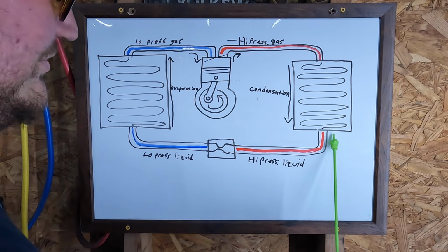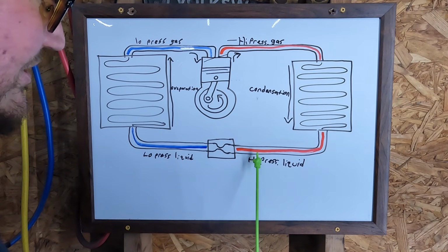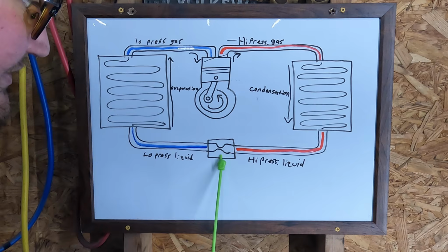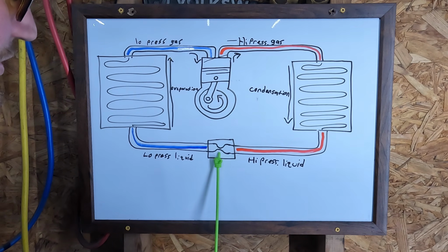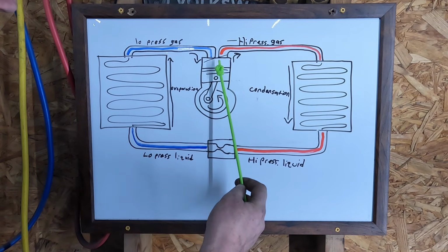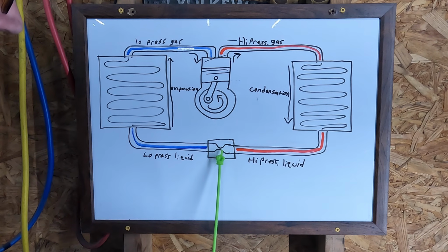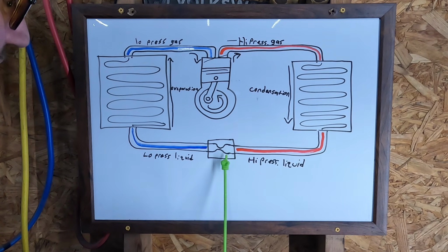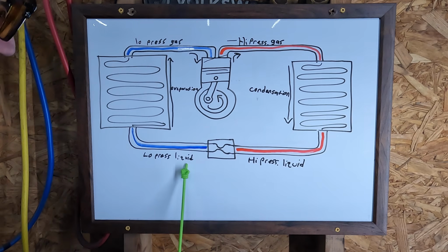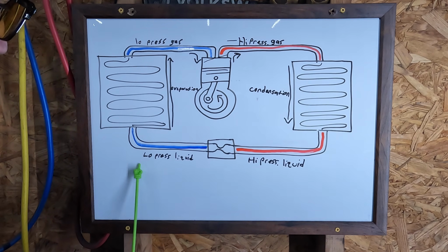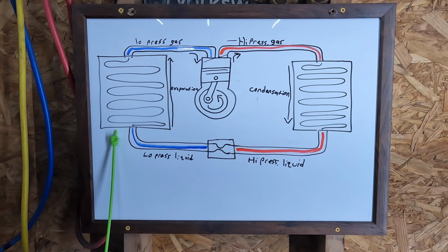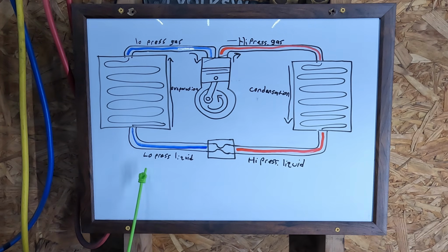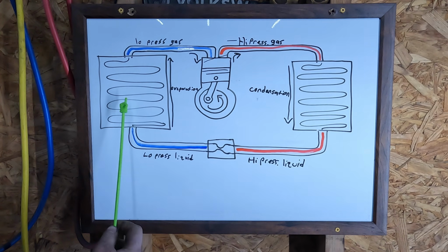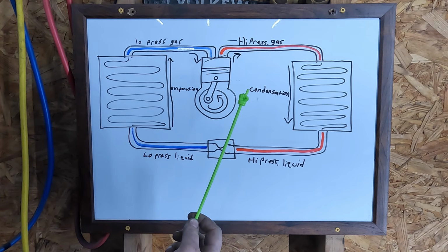So out of the condenser, we have a high pressure liquid coming over here to the expansion valve. This is just a very specific sized hole, what provides resistance for the compressor to build pressure behind. And as the high pressure liquid crosses that restriction, it's going to become a low pressure liquid and then go up in here to the evaporator. So now that the refrigerant is a low pressure liquid, it's going to want to turn back into a gas. And to evaporate, it needs a bunch of energy.